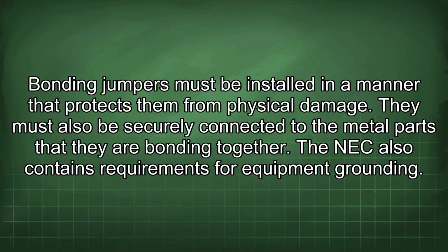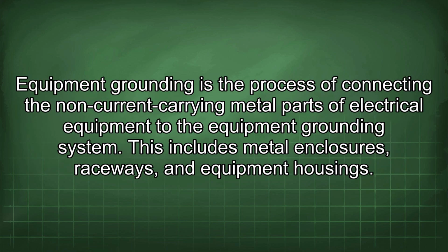Bonding jumpers must be installed in a manner that protects them from physical damage. They must also be securely connected to the metal parts that they are bonding together. The NEC also contains requirements for equipment grounding. Equipment grounding is the process of connecting the non-current carrying metal parts of electrical equipment to the equipment grounding system. This includes metal enclosures, raceways, and equipment housings.